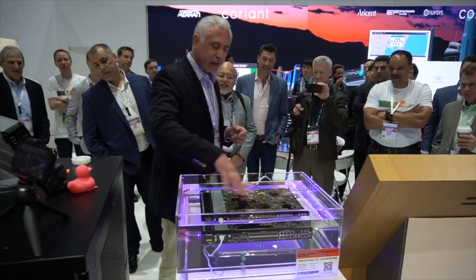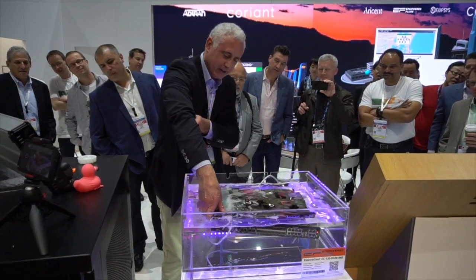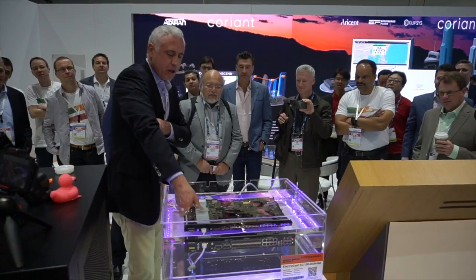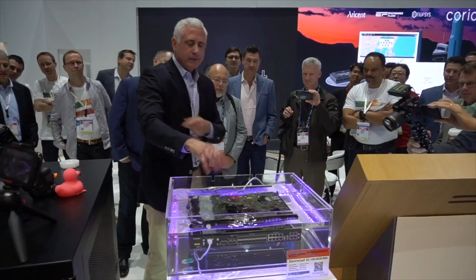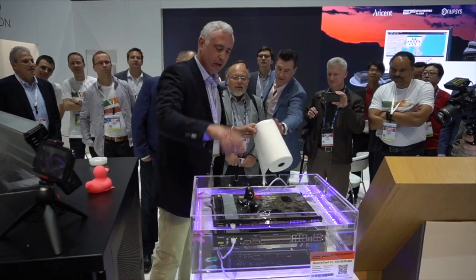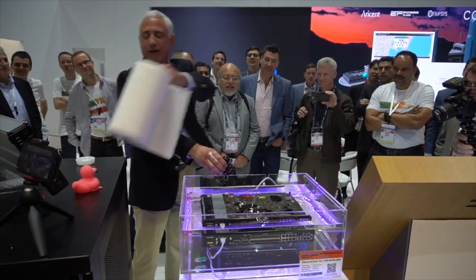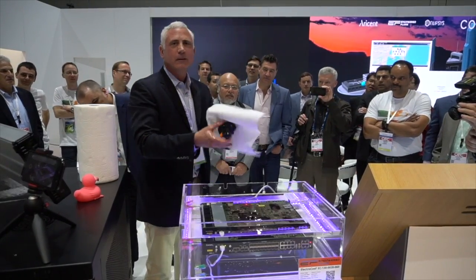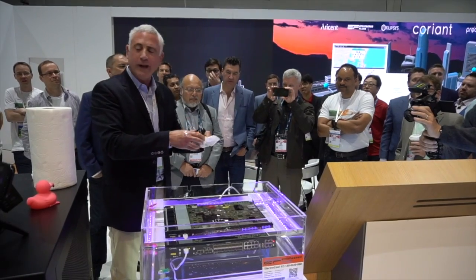A little slipperier than water. The viscosity here is slightly thicker than water. Now, the question is, is it still working? Let's pick it up and find out. Oh, there are our fans. We want to see if our ducky floats — oh! That's the problem. They're designed for water. This fluid is 80% the weight of water, so it's lighter and less dense than water. The viscosity at room temperature is about twice that of water.